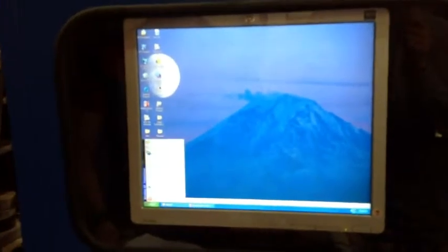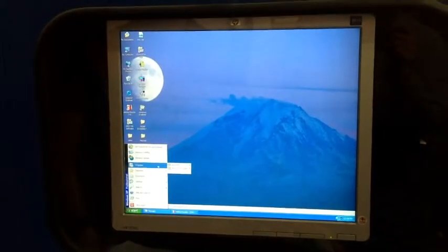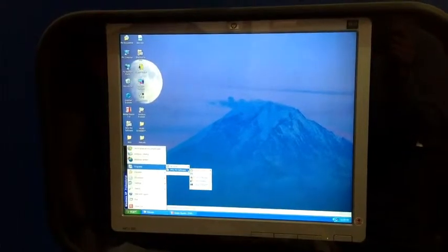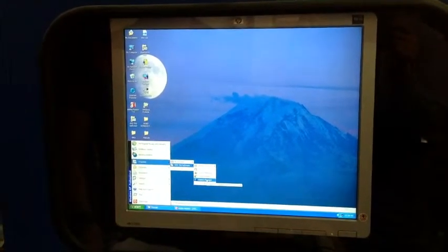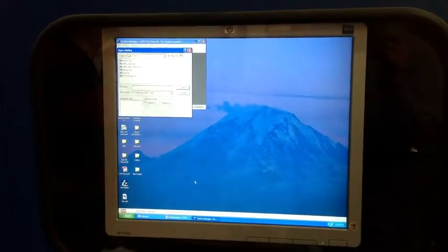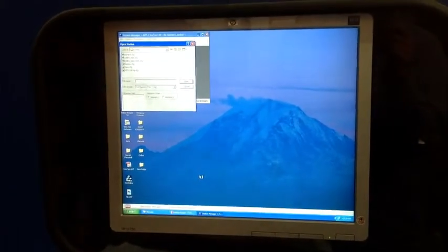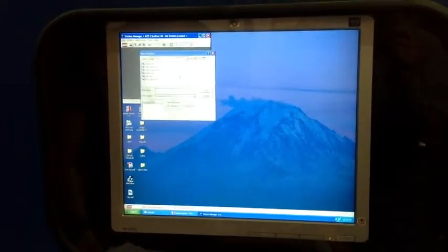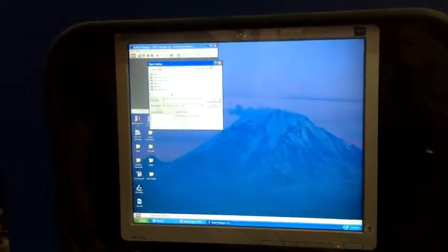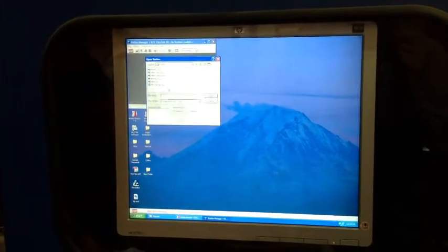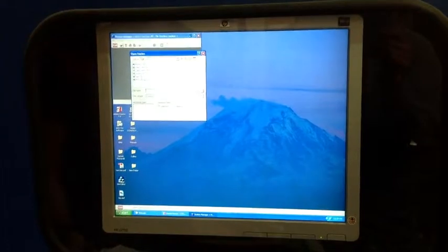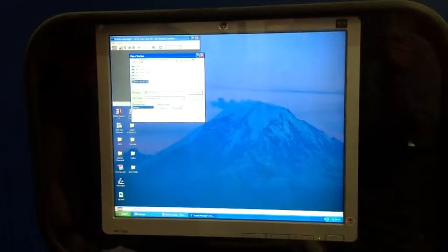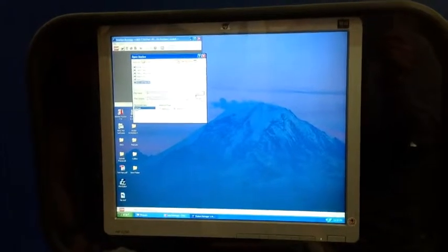What you will need to do is to click start, program files. Then you go to MTS 793 software. Then you click on station manager. After the click, there's several windows that are going to pop up. And in this window, it allows you to select the station you want to use. Like I said before, I will encourage you to use the default one that comes with the software, which is mts100kip.cfg. Then you click open.